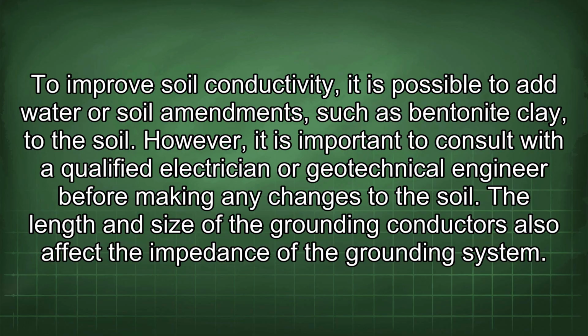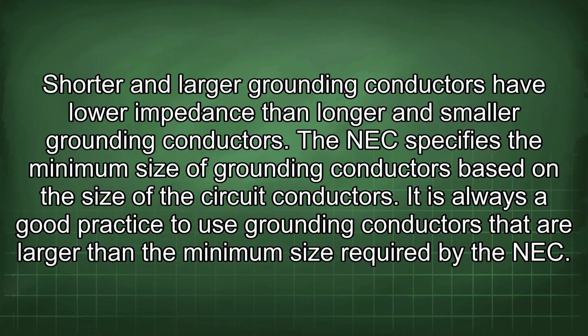To improve soil conductivity, it is possible to add water or soil amendments such as bentonite clay to the soil. However, it is important to consult with a qualified electrician or geotechnical engineer before making any changes to the soil. The length and size of the grounding conductors also affect the impedance of the grounding system. Shorter and larger grounding conductors have lower impedance than longer and smaller grounding conductors. The NEC specifies the minimum size of grounding conductors based on the size of the circuit conductors.